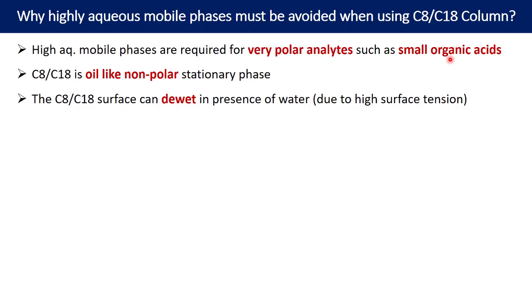This de-wetting happens because water has high surface tension. Water flowing over the stationary phase will not enter the pores but will just pass through the spaces between the pores. The pores never open up, and since the stationary phase lies inside the silica pores, if the pores are not wetted, the stationary phase will not be in active mode — and that is the primary reason for trouble.